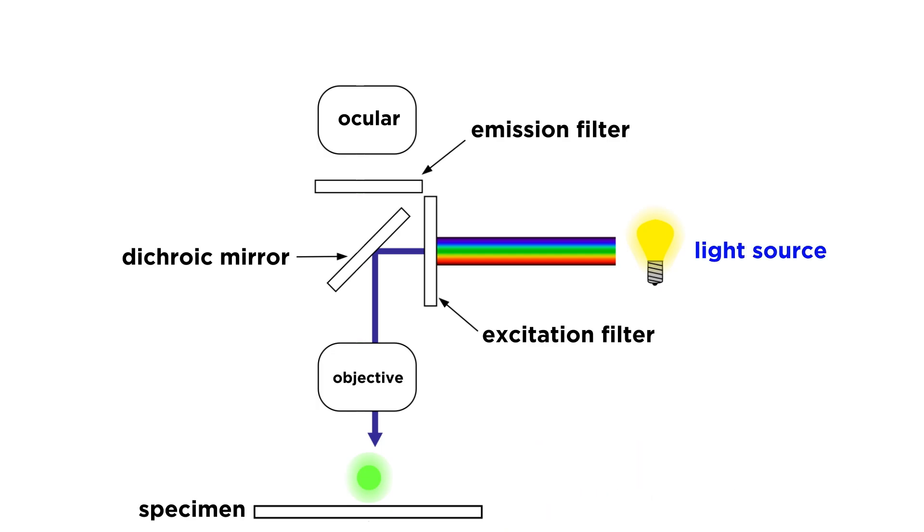Next, the laser emits a photon of light, which passes through an excitation filter that only allows photons of a certain wavelength to pass through. Dichroic mirrors then angle the photon beam through the objective lens that focuses the photon onto the sample. The photon reaches the sample, which in turn emits a photon of lesser energy.